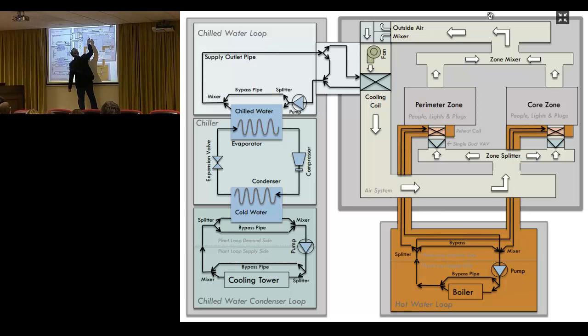No, we're recirculating this, right here. So we're mixing this return air with some outside air, and this is where most of the cooling occurs. We cool the air, then distribute it. Sometimes we need to reheat, when the air is a little too cold - just right for this, but too cold for this. Not that important. So we use cold air, about 16 degrees Celsius, normally the supply air temperature.